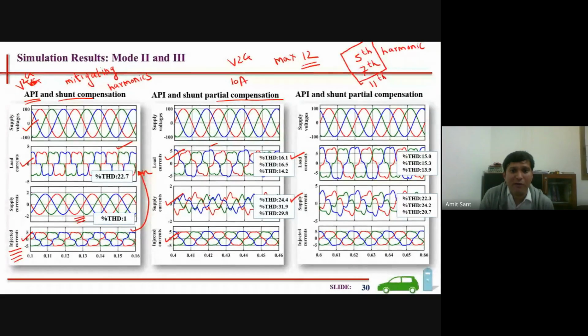But the active power that was delivered by the grid is also reduced. That means now the fundamental current is coming from here. Let's say 60% of the fundamental is coming from the battery, 40% is coming from the grid. So what is THD? THD is the square root of the sum of squares of harmonic currents divided by the fundamental component. Fundamental is reduced. That is why the THD has increased. Right? This is not degrading the system, but because your fundamental has reduced, your harmonics have gone high. Any point of confusion here?